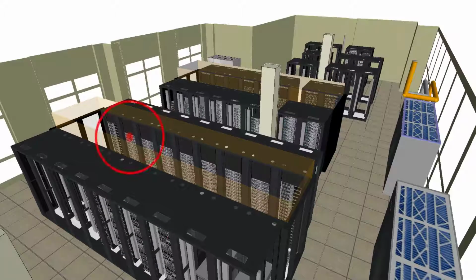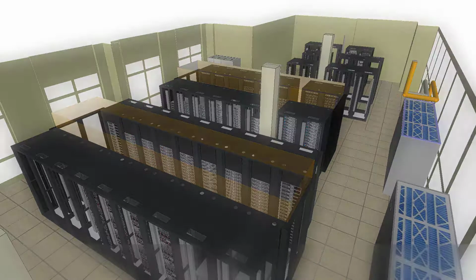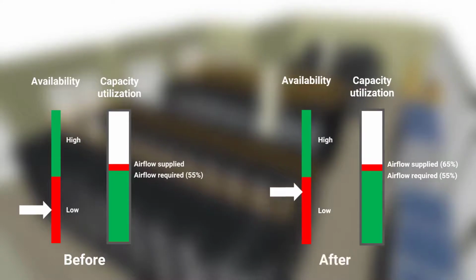The inability to predict data center behavior not only caused this problem, it also greatly limited the visibility of options to solve it. There was only one option the data center management team was certain would fix the problem, and this was to cool the whole room down until the alarm stopped. So this approach eliminated the potential outage, but at the expense of capacity utilization.